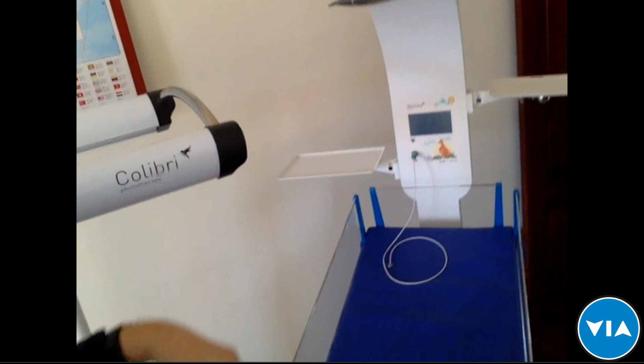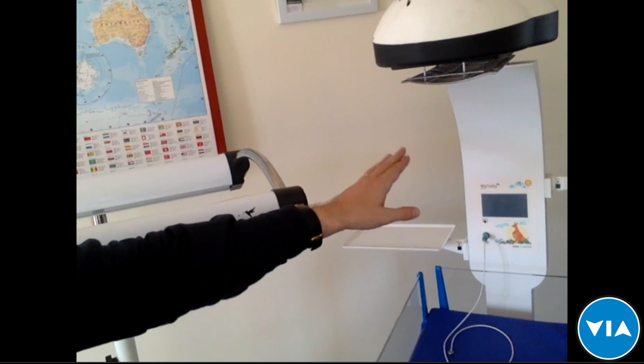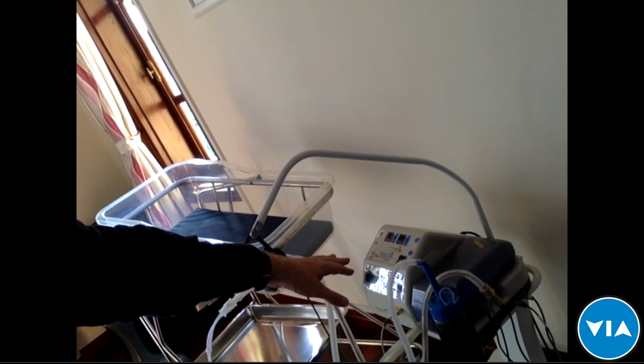For Wallaby Warmer, we don't have the battery backup like that yet because it's operated on 220 volt AC, the heater element, and that would be a little more complex. But we do have a small battery backup in this device that keeps the machine on without providing the heat, so just for monitoring at the time, and that's for about 2 to 3 hours. The same small battery is in the Dolphin CPAP, so we can keep the machine alive for about 3-4 hours, but without providing heat for heating up the gas and the humidifier.